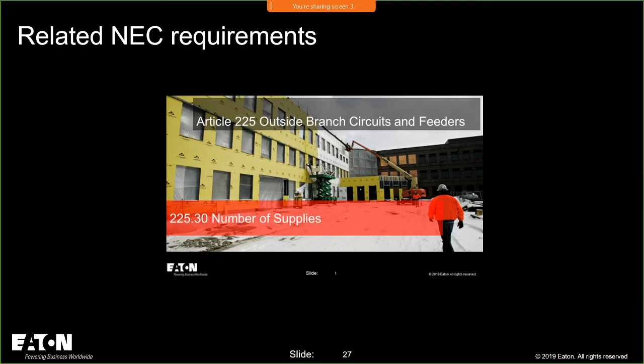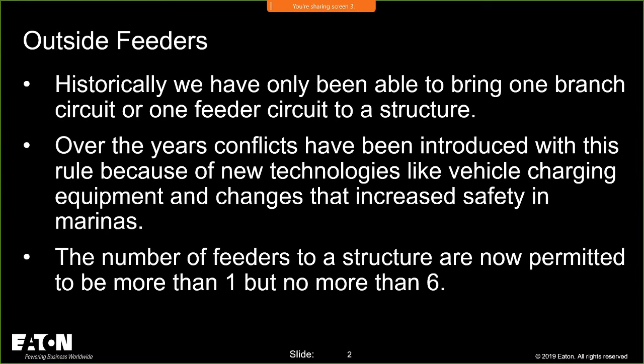Historically, on these outside feeders, we've only been able to bring one branch circuit or one feeder to a structure. Over the years, under certain circumstances, that's changed, but for the most part in a lot of these areas, we weren't able to bring more than six feeders out. Over the years, we've had conflicts with things like electric vehicle charging equipment, which we talked about a little, and marinas. We've wanted to bring more than six disconnects or feeders, but we weren't able to do that.